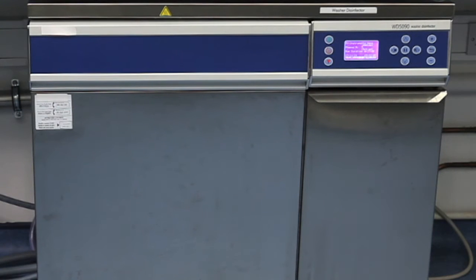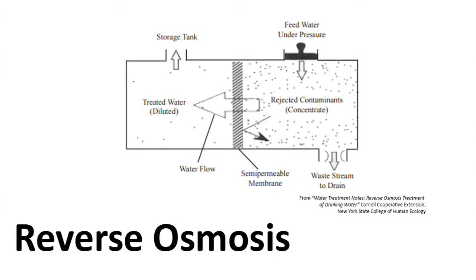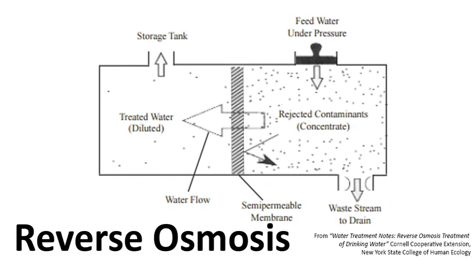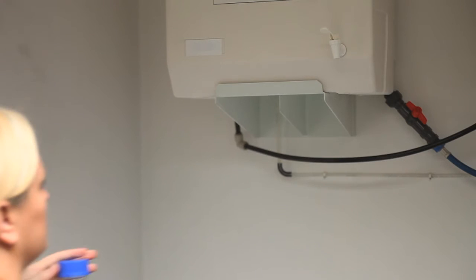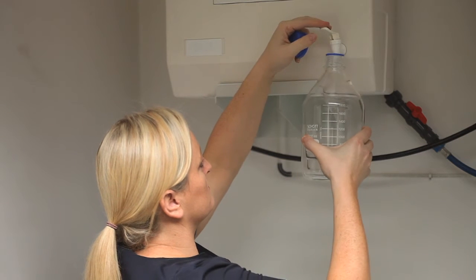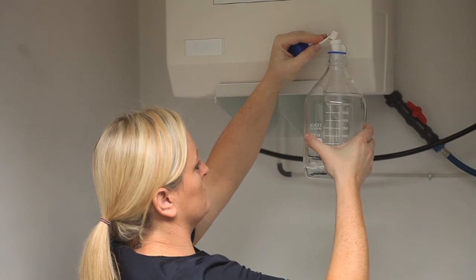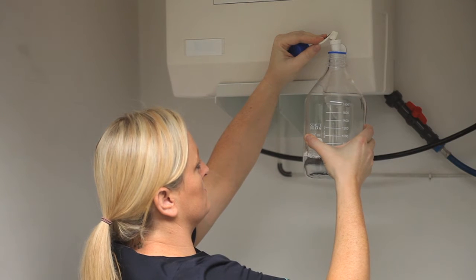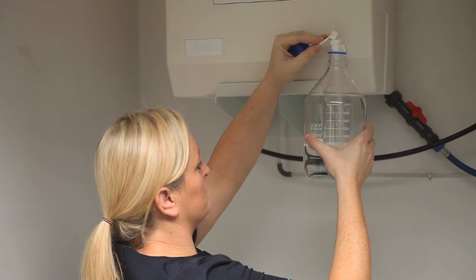The manufacturer's instructions will guide you to the type of water and cleaning agent to be used in the washer disinfector. The washer disinfector must have specially treated water supply, such as reverse osmosis generated water. Reverse osmosis, RO, is a technology that uses a semi-permeable membrane to purify water. It does this by removing large particles, including bacteria and many types of dissolved molecules and ions, from the water supply. The purified RO water is collected and can be used directly or stored for future use. Dissolved chemicals and particles present in the original water supply do not pass through the RO membrane. RO technology is commonly used to generate drinking water from seawater.